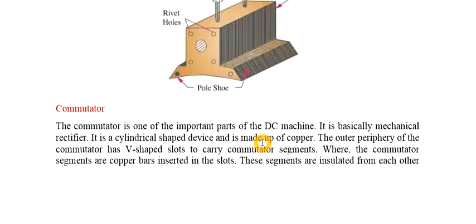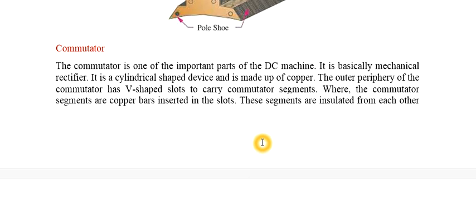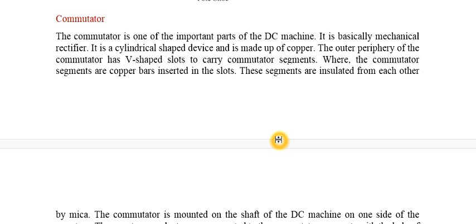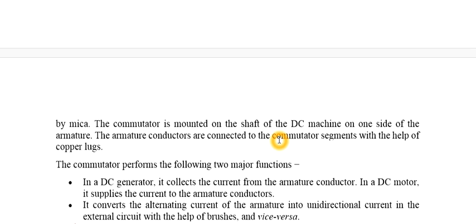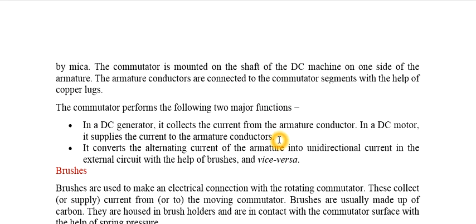The commutator is a very important part of the DC machine. It works with brushes to convert bipolar AC current to DC current, so it is called a mechanical rectifier. It is a cylindrical-shaped device made of copper, with several slots carrying commutator segments. These copper bar segments are inserted in the slots and insulated from each other through mica. The commutator is mounted on the shaft on one side of the armature.